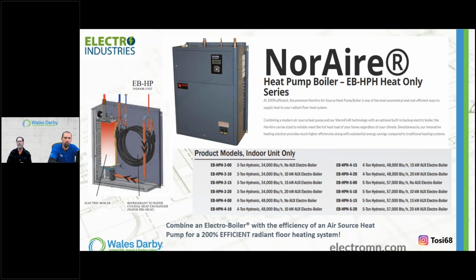But they also do a nice add-on if they have the option, because let's be realistic, with refrigerant we're going to run out of BTU capacity. And now what do I do? I ripped out the boiler, right? Space was at a premium. So now I can actually buy one of these magic NorAirs with or without an electric boiler inside. So that will only come on if needed, or fully take over, or play nice as a hybrid in between. In addition, if the boiler was still there, you now have redundancy, fuel choices, and also serviceability if you should need it during some kind of crisis in the middle of the winter.